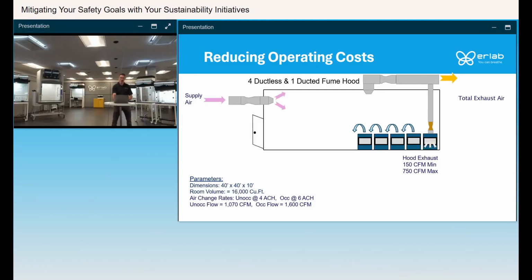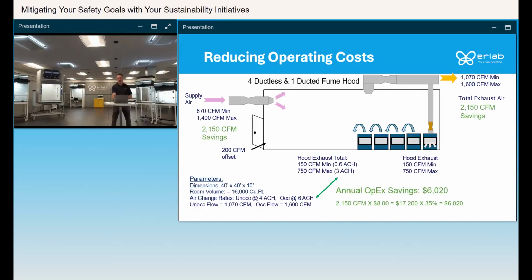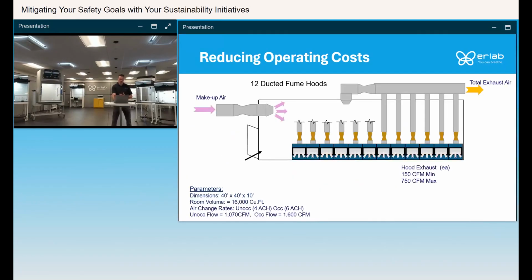But in this example, when you change those 5 ducted fume hoods and go with 4 ductless and 1 ducted, you're going to significantly eliminate the amount of makeup air needed. So you can stay at the minimum air change rate within the space, because that 1 ducted fume hood is only going to be at 3 air changes per hour. And with this example, you'll see they save about $6,000 a year in operating expense, and that's just in the makeup air. And you'll see an even bigger savings if you go to a larger lab with 12 hoods.